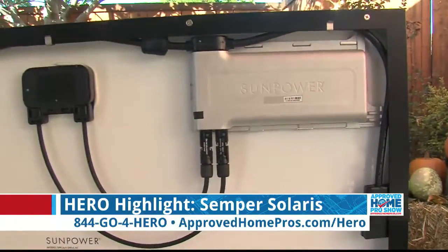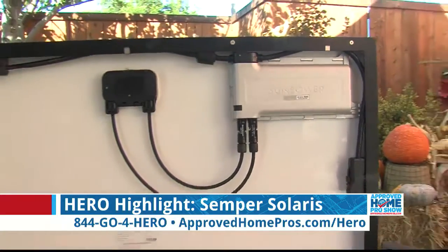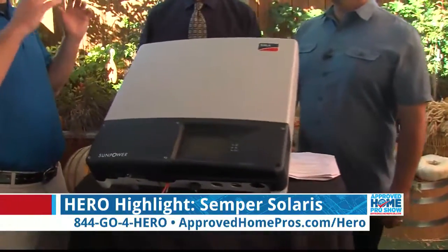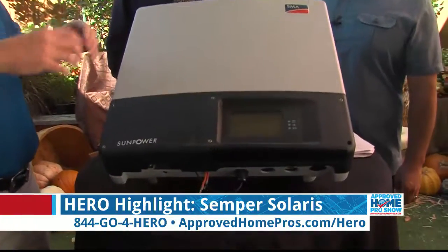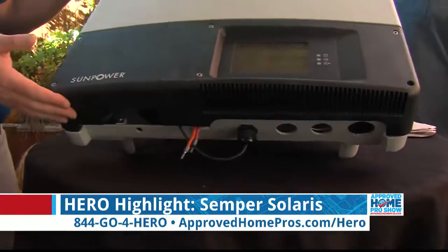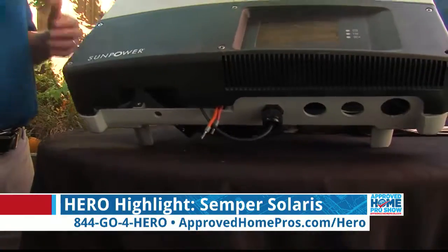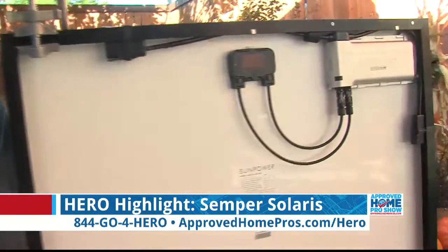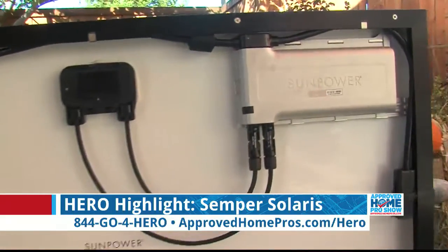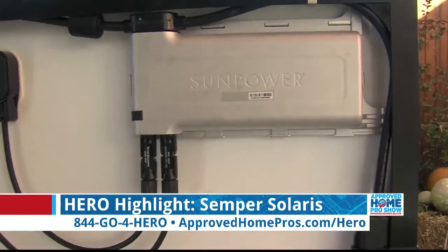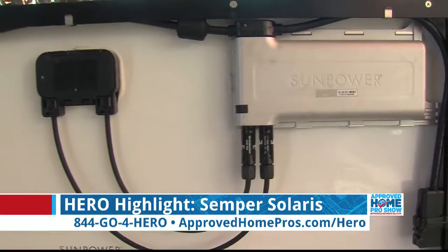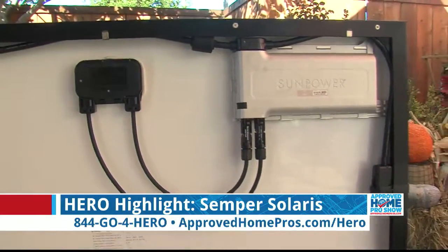The main differences between the two is that with a centralized string inverter, you have your entire system wired together, and all of the modules are wired in series and then into parallel, and goes into one large centralized inverter. With microinverters or AC PV, which is this one here, every module is independent from the one next to it, and every module has a miniature microinverter or AC PV directly underneath it.